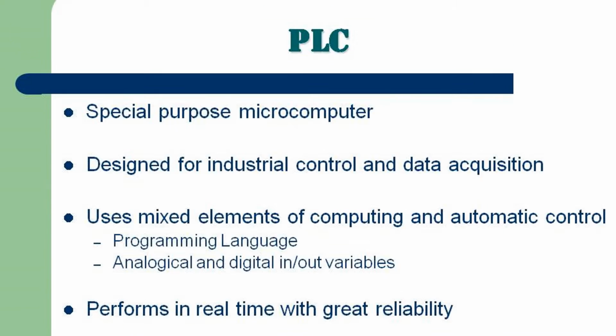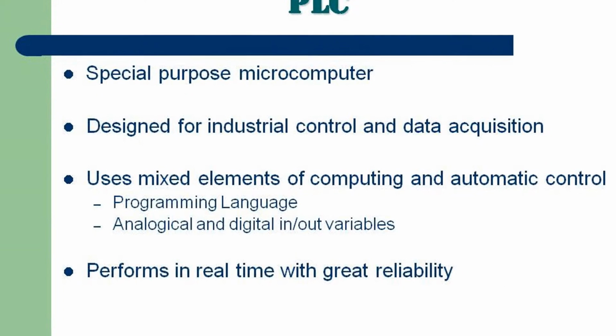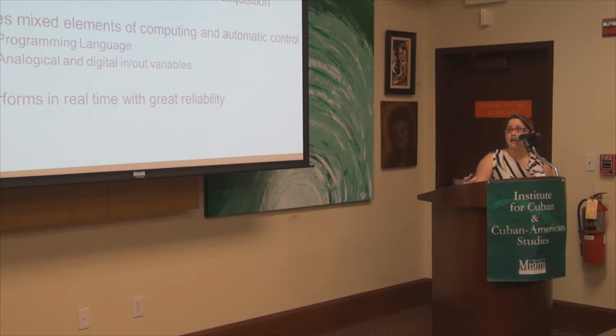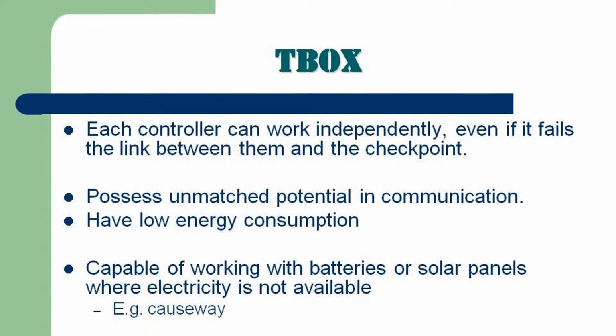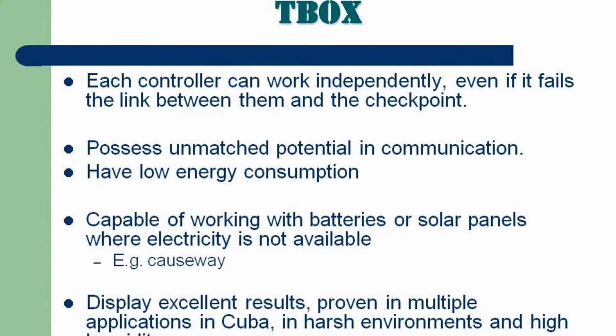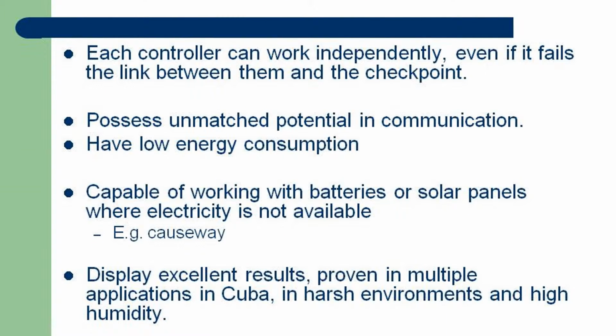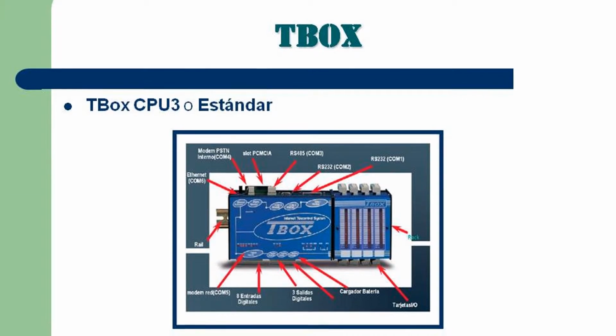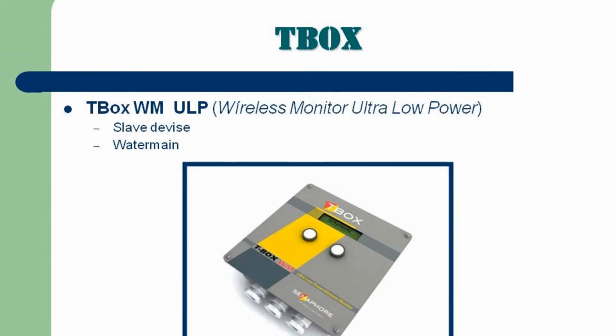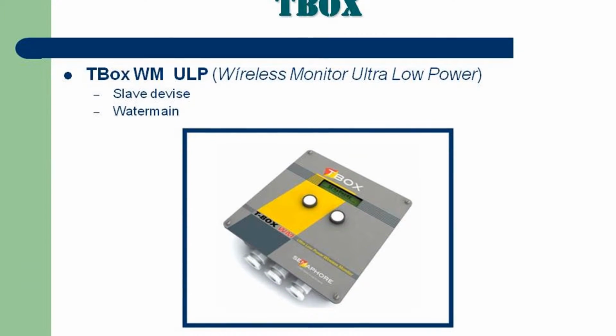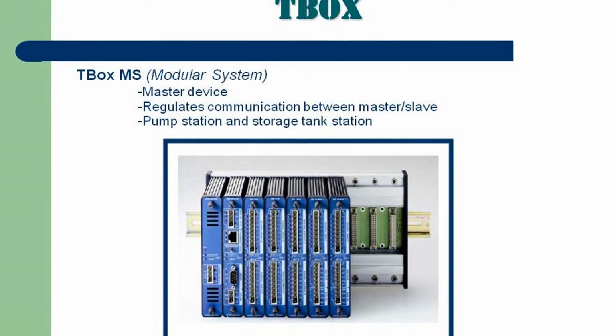Then we have the PLCs. They're a special purpose microcomputer. They're designed for industrial control and data acquisition. They use mixed elements in programming, and they perform in real time with great reliability. The brand of PLCs used in this project is the T-Box. Each controller can work independently even if the connection fails. They possess unmatched potential in communication and have low energy consumption. They can operate on battery or solar panels. They display excellent results proven in multiple applications in Cuba, in harsh environments and high humidity. Here is a diagram of what a standard T-Box looks like. This is the wireless monitor ultra-low power T-Box, which is going to be located at the water main to measure pressure. And the modular system T-Box is going to be located at the pump station and storage tank station.